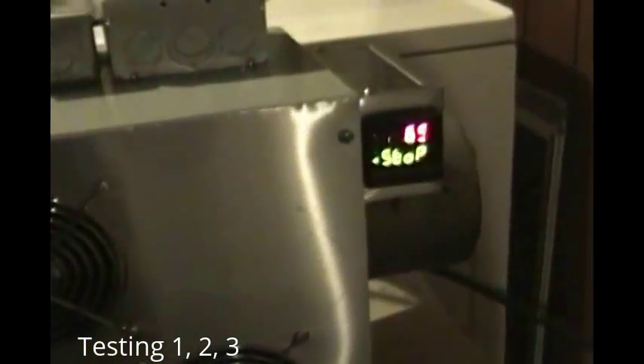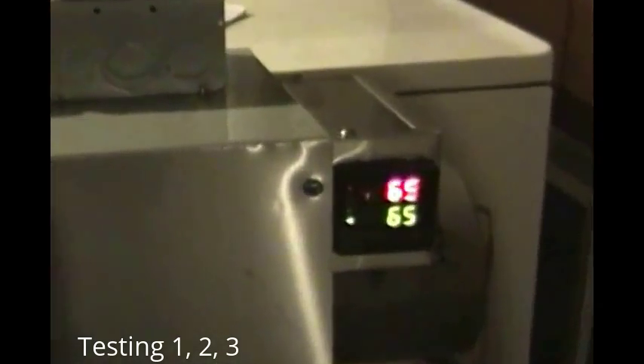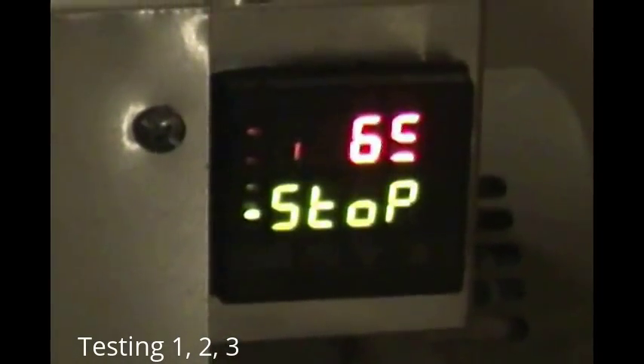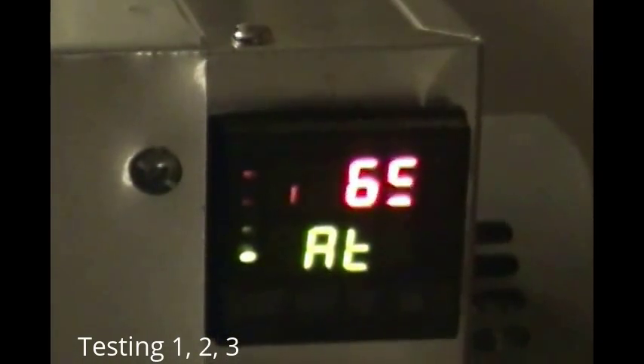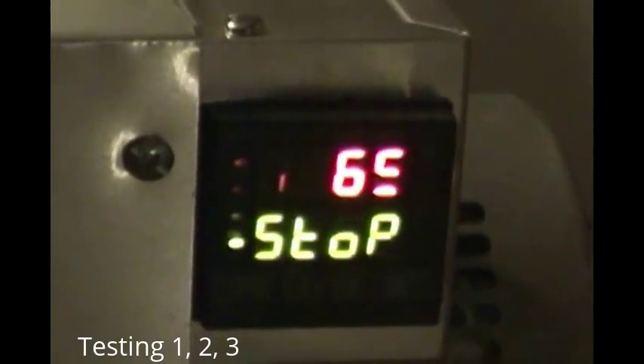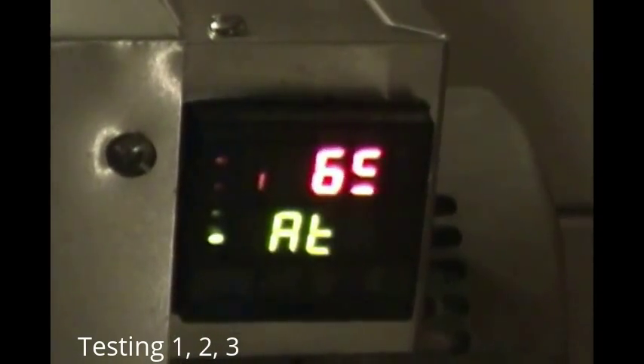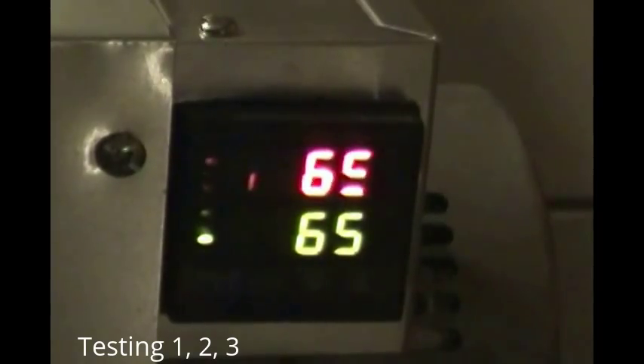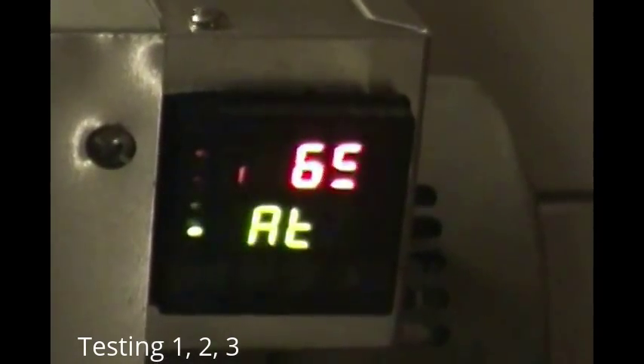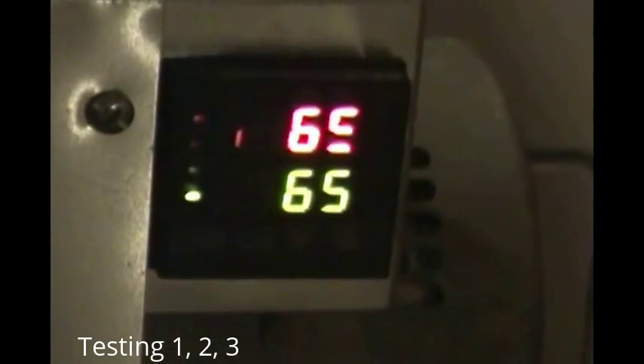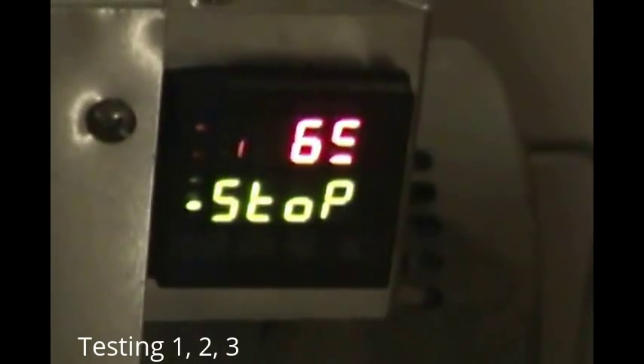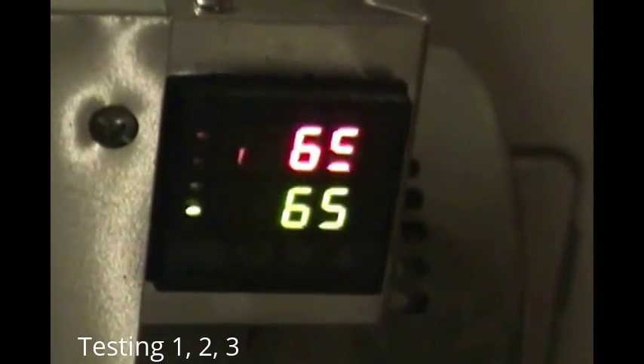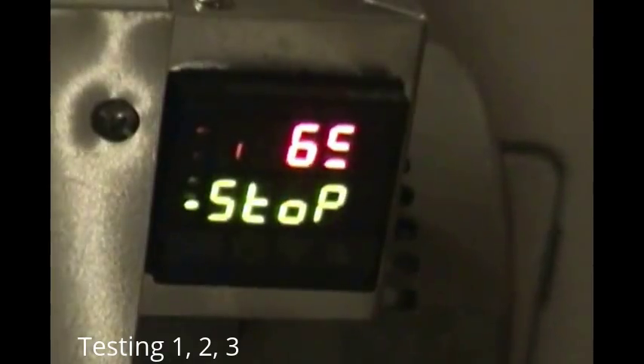So if we go over here and look at the PID, can you zoom in on it? Currently at 65 degrees ambient temperature. I have the PID programmed with auto tuning to achieve 420 degrees Fahrenheit within 11 minutes.